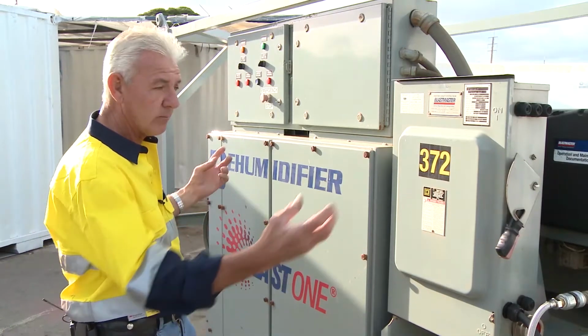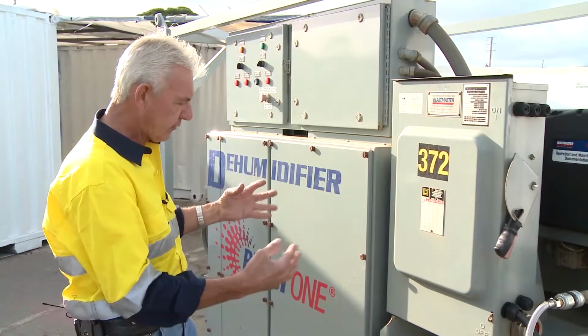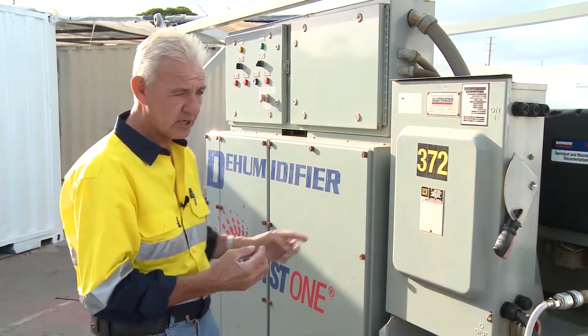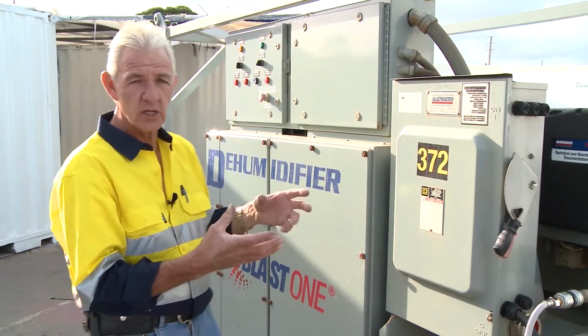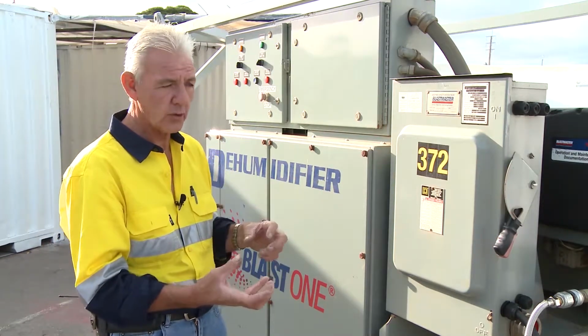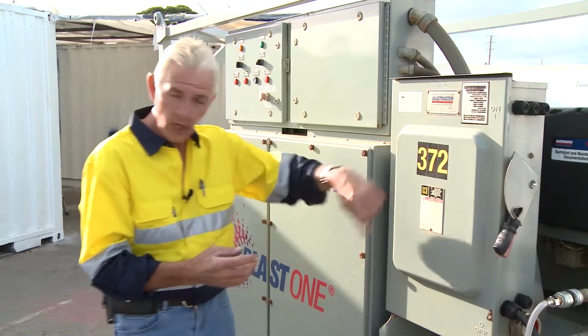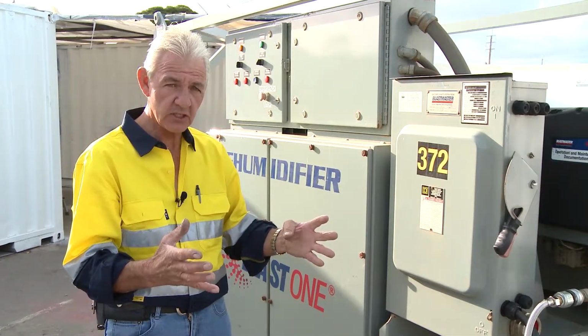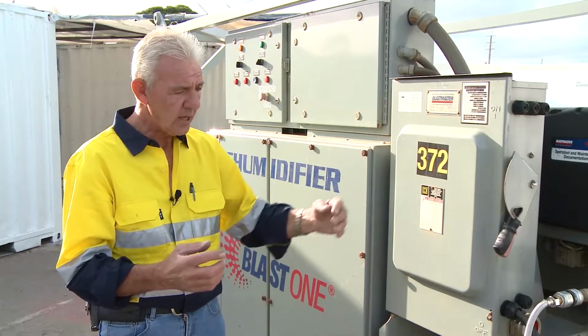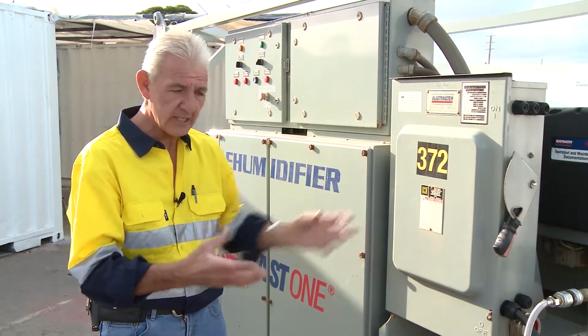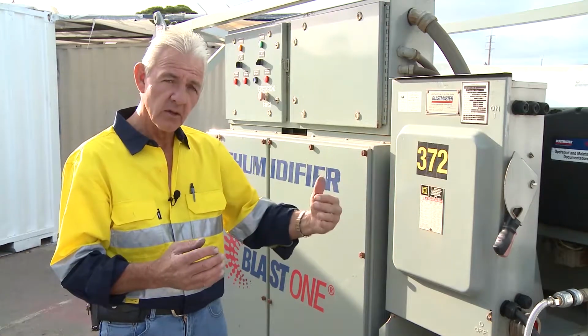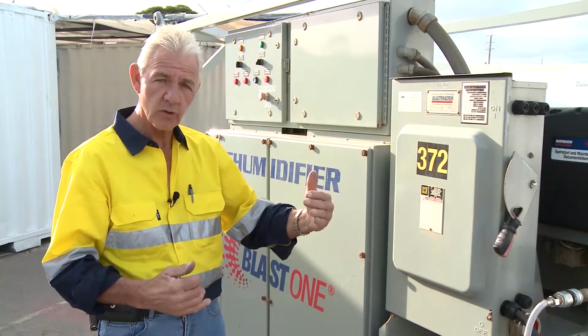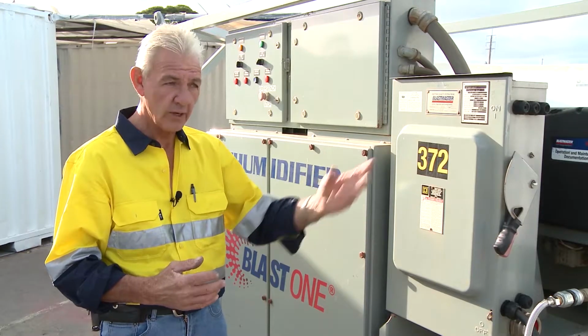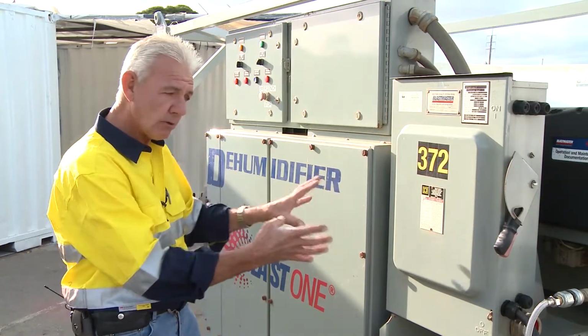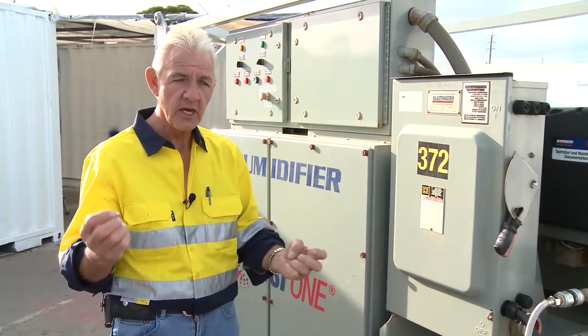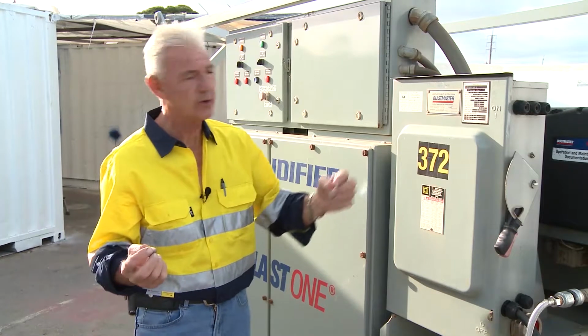You've got air being drawn from the atmosphere, run through the machine, processed and exhausted on the other side. So I'll show you how to appropriate the ducting in relation to what your requirement is, so I can recirculate the air within the encapsulation that I've designed or erected. Also, if I don't wish to maintain that encapsulated, I can have it drawn from atmosphere and totally fill the unit or encapsulation with ambient air from outside, but still process through this particular machine. So you can see it's got the adaptability to do what I want it to do.